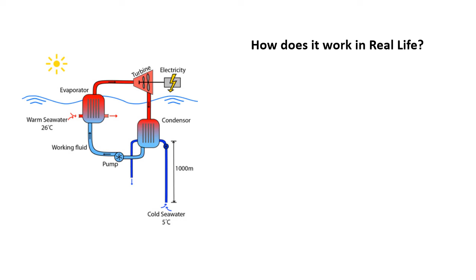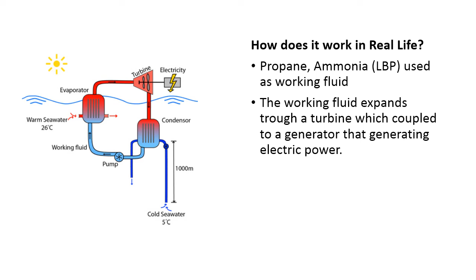We are using propane and ammonia as a working fluid, not seawater. We are not using seawater as a working fluid. We are just absorbing heat from the seawater and transferring it to propane and ammonia, which have a low boiling point. This liquid is used as a working fluid, which in turn goes to the turbine. The turbine produces electricity and the fluid goes back to the condenser. The cold water from below 1,000 meters is pumped to the condenser, which is used to cool it, and the working fluid is again circled back to the evaporator.